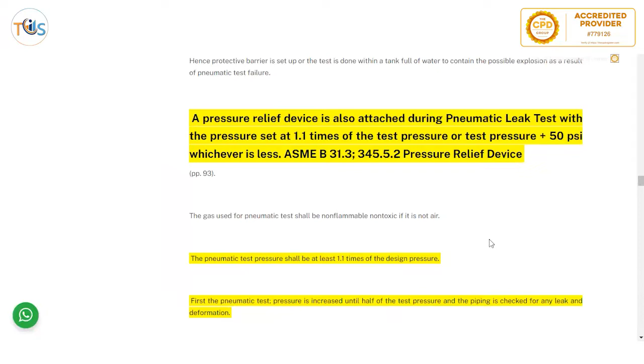So practically, what does it mean? If the design pressure, say, is 100 psi, you do the pneumatic test at 110 psi, and the relief valve is set at 1.1 times the test pressure, which in our case was 110 psi. So 1.1 times 110, I think it would be 121 psi. Okay, and 121 is less than 110 plus 50 psi. So that's good enough.